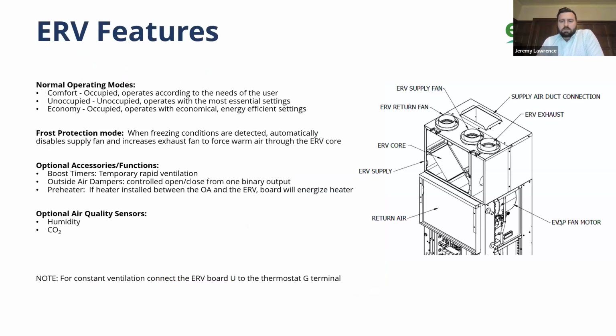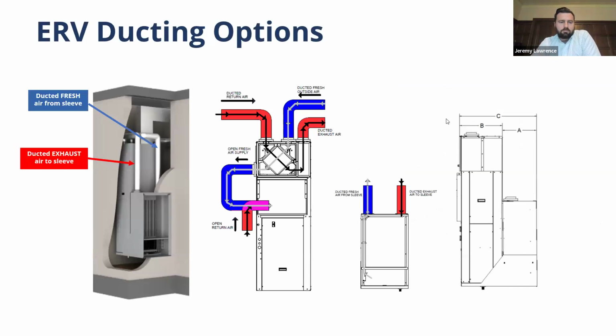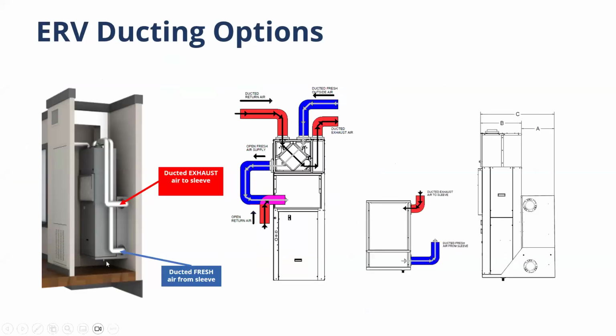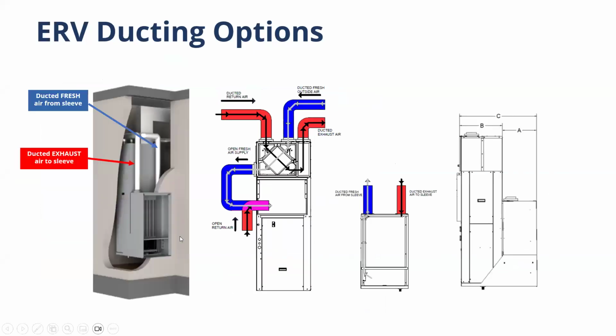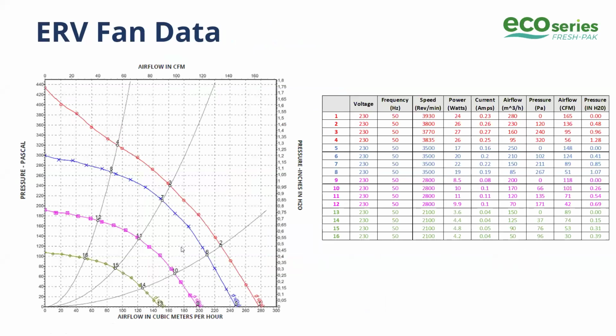We talked about some of these pieces, but this is how the unit kind of looks. So fresh air and exhaust are vented into the sleeve. The ERV return can be ducted into the space, or it can just pull from around the unit as well. And then the supply can go right into the ductwork or also be ducted around. There's a piping configuration. We can get a good picture of how the unit is installed, either with the side or the top ERV ports built right into the sleeve, through these pictures. And then this was the ERV fan data that I was referring to. Again, if you want to dig deeper into this, we can certainly schedule a more one-on-one time to do that.